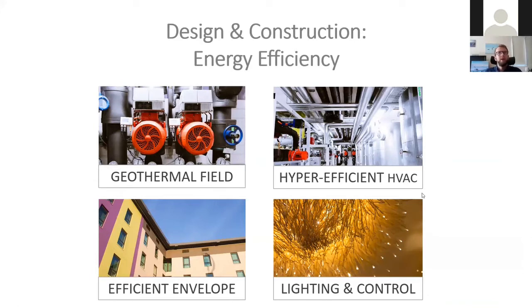Then a couple of energy efficient technologies were installed. We have a geothermal or geo-exchange field below the basement footprint of the hotel. In essence, 100 boreholes were drilled into the ground, each about 65 meters deep. A U-bend of pipe was installed into those holes that goes down and comes back up. The pipework was connected together horizontally in a very specific way, and we now have about 13 kilometers of high density polyethylene hard-wearing pipe in the ground that we use as a heat exchanger.